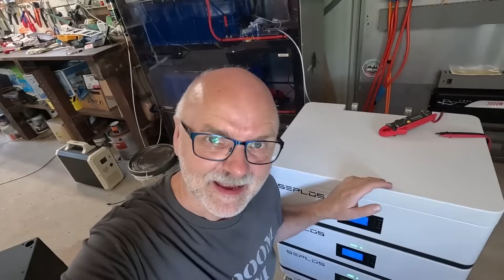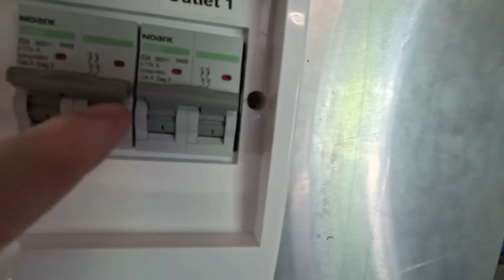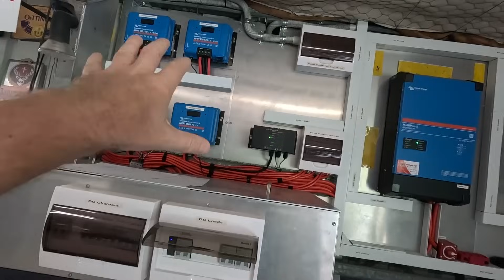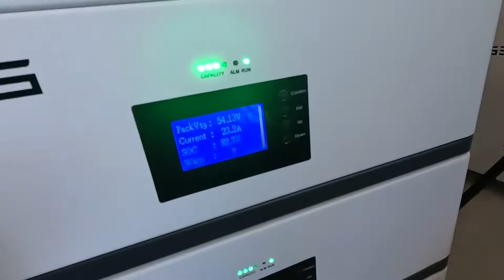See, with such a setup now, I am not able to change the CCL quickly with all these batteries here. I would need to disconnect the communication between all the batteries, connect to each of them, and set the CCL a bit higher, maybe 25 or 30 amps or something. And the reason I'm limited to 60 amps in total is solely the circuit breaker here carrying all my load. This is connecting this battery now to our battery shelf, charge controllers, the Multiplus units, the Phoenix inverter - everything is running from the Seplos battery now, but we are limited by this breaker here, 63 amps. That's why I'm asking only for 60 amps charge current, continuous charge current.